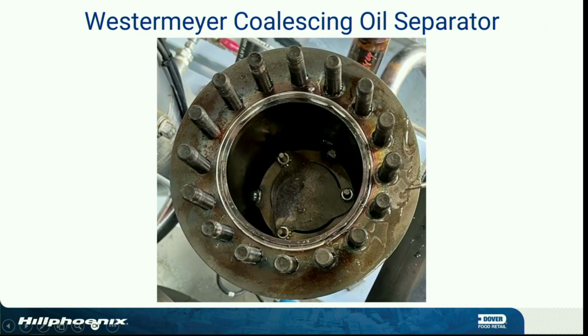Yep. But anyway, you're going to pull back. I call it a strong back. People call it a shuriken. But you'll notice that it rotates counterclockwise to get the little tabs into the screws. I complained about that because when you take it apart, put it back together, and start tightening that wrench up, it pushes those tabs away. Well, they have changed that now. Now it's clockwise. Now the tabs are on this side. And eventually you're going to get a nut, guys, welded on right there to help get that thing out, because it's tough when it's hot. All right?